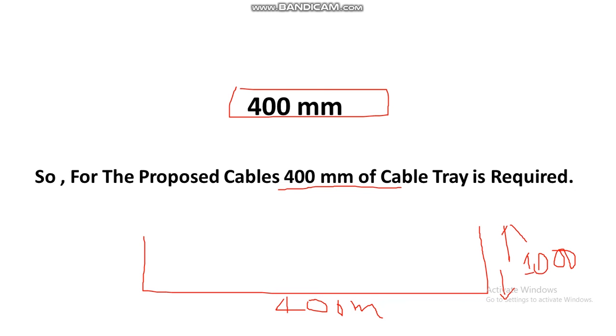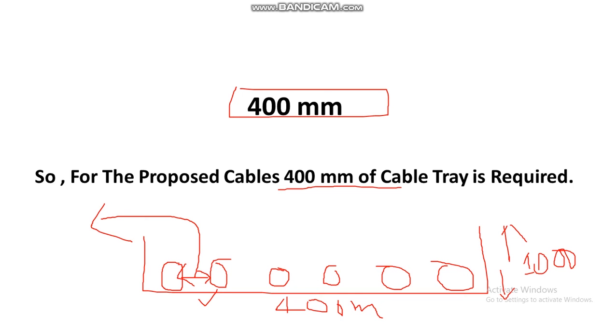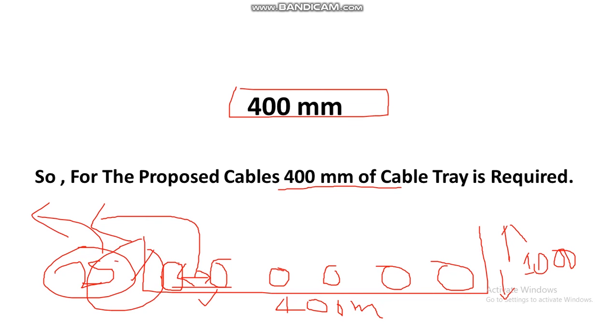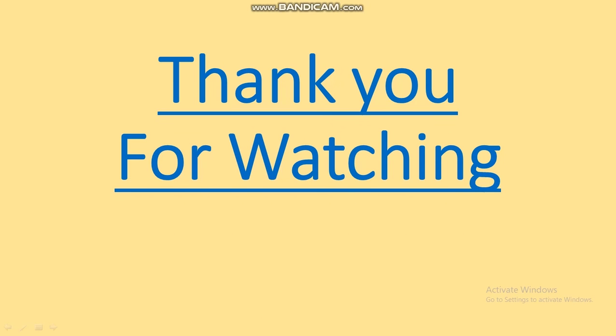So we have calculated the cable tray size for our six cables: three runs of 300mm², two runs of 120mm², and one run of 70mm². The final cable tray size is 400mm width and 100mm depth. Remember to maintain a spacing gap of 25% of the cable diameter between two cables during installation. Thank you for watching — please like, share, comment, and subscribe, and hit the bell icon for upcoming video notifications.